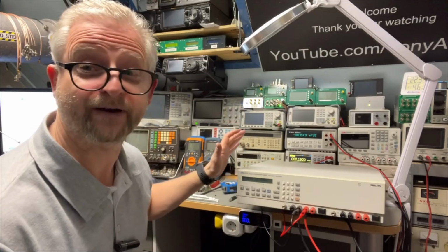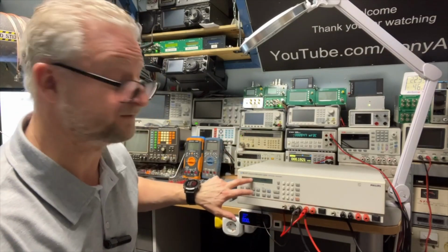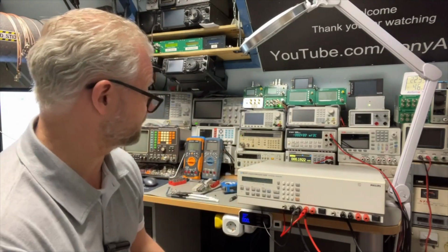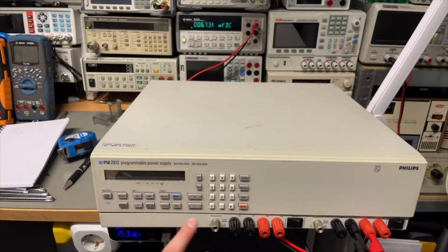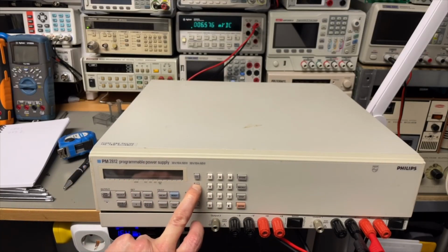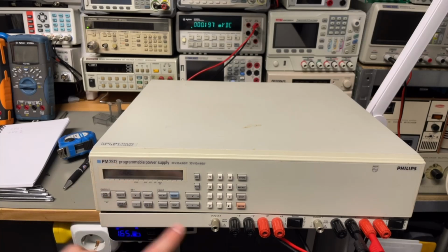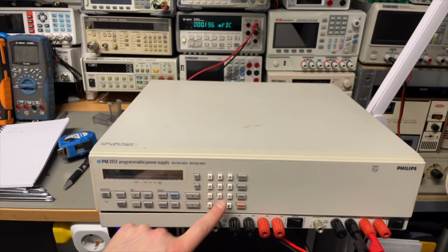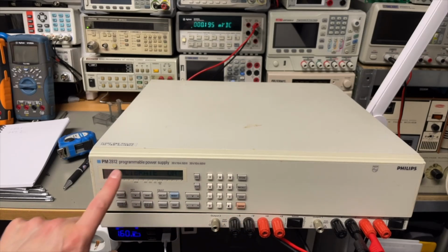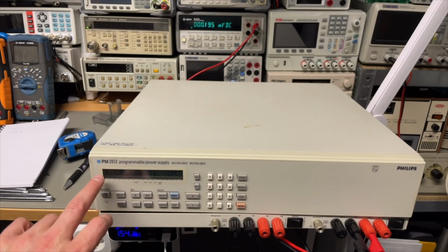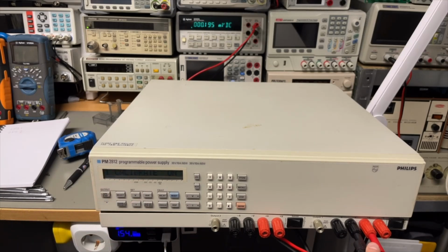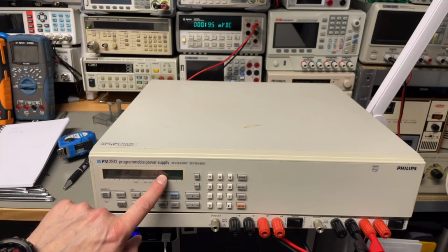I'm in, it says calibration on. You push enter, and now it says VCAL low. Let's see what we need to do. Device is off, you hold the aux button, you power on the device. It says initializing, you keep pushing, then it says code, we use 2812 — probably if you have a higher model, you just type your model number. Then it says calibrate on, and I'm on channel 1. I say enter, then it says voltage calibration low.